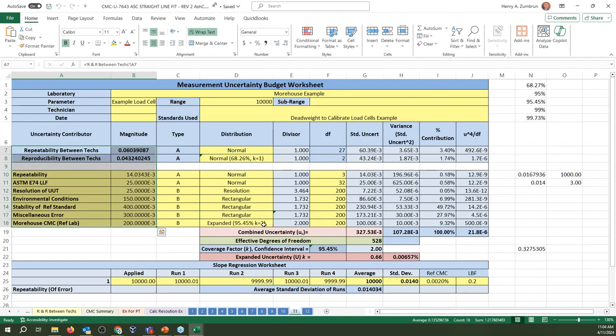But what you can do is look at the different points in this sheet. Here's the 10,000 pound point. Here's R&R between techs. Here's repeatability. We can ask, what's our largest source of error here? On this sheet, the largest source of error is the stability of the reference standard from one calibration to the next. So if I wanted to lower my uncertainty, knowing that's our largest source of error, I would decrease the stability. Maybe it's something else that's going to be the largest source of error.